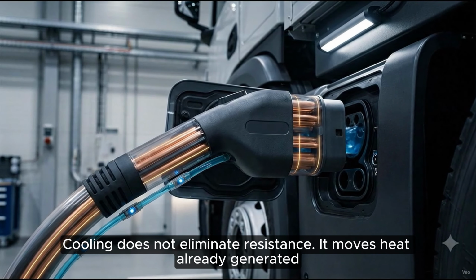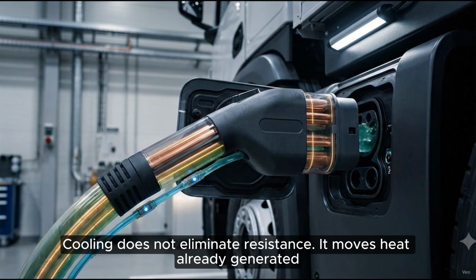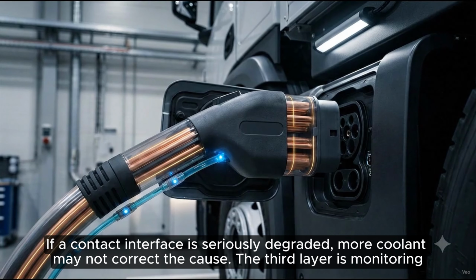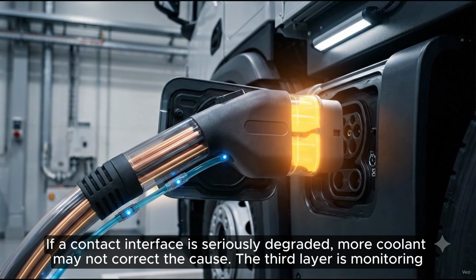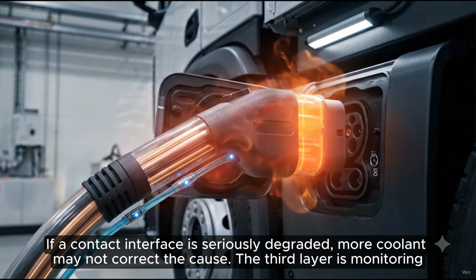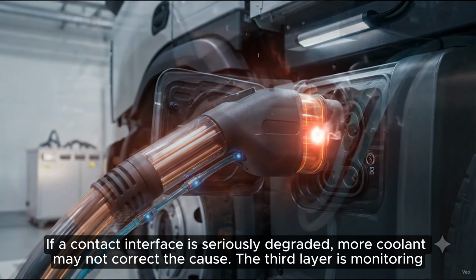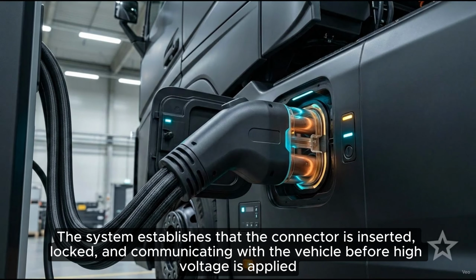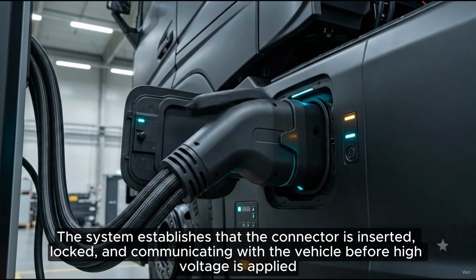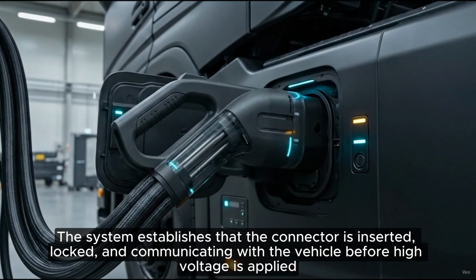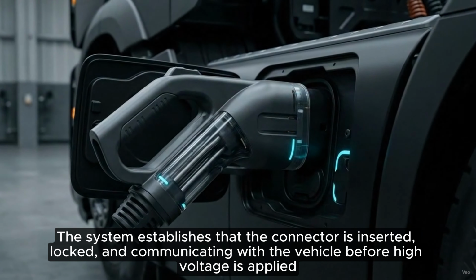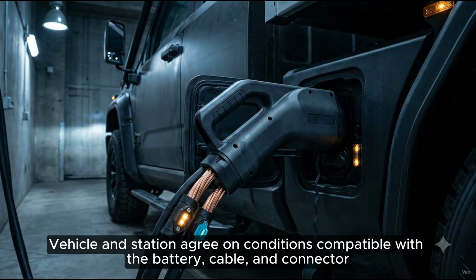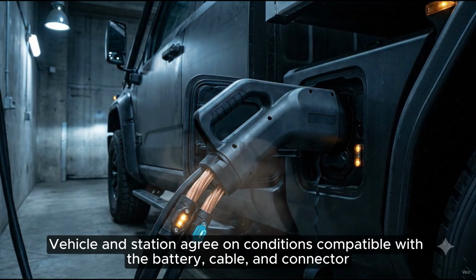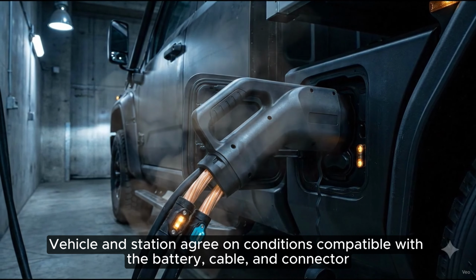Cooling does not eliminate resistance. It moves heat already generated. If a contact interface is seriously degraded, more coolant may not correct the cause. The third layer is monitoring. The system establishes that the connector is inserted, locked, and communicating with the vehicle before high voltage is applied. Vehicle and station agree on conditions compatible with the battery, cable, and connector.